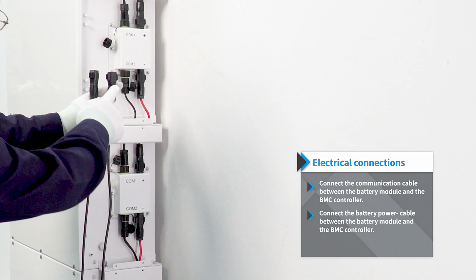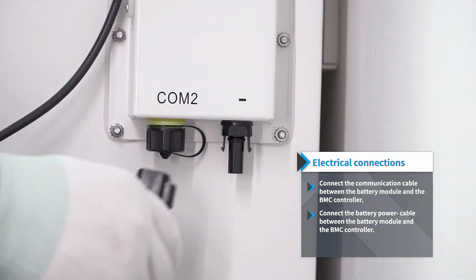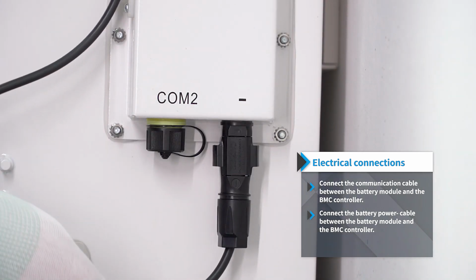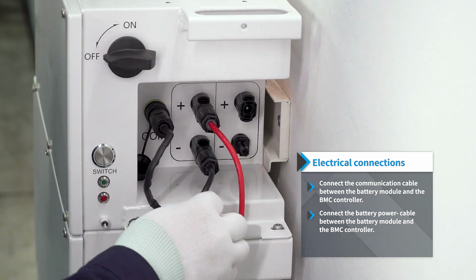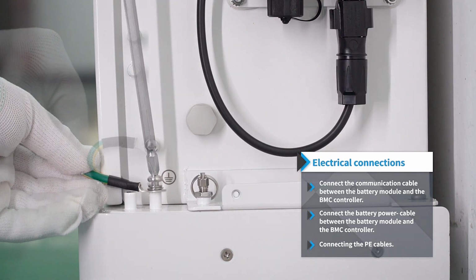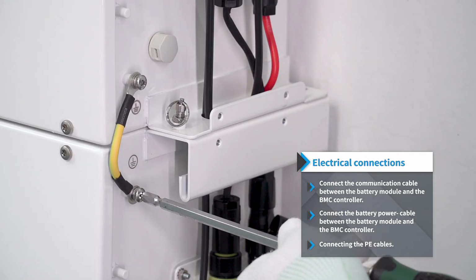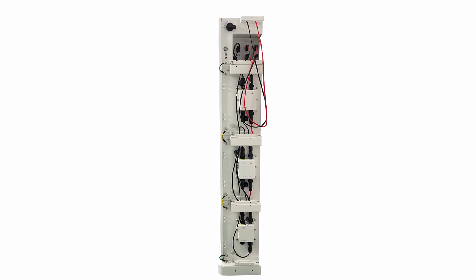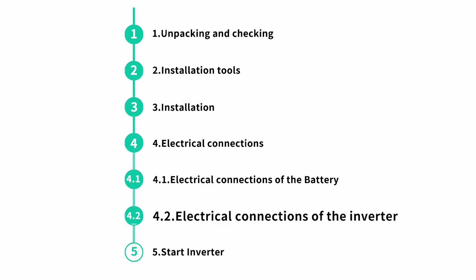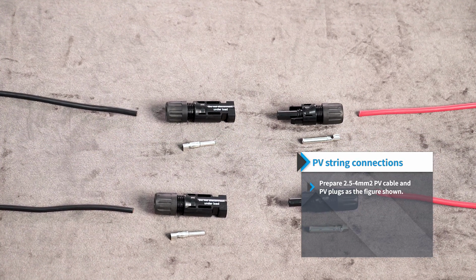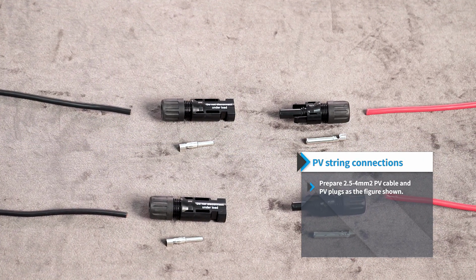Connect the battery power negative cable between the battery module and the BMC controller. Connecting the PE cable. Electrical connections of the inverter. Prepare 2.5 to 4 square millimeters PV cable and PV plugs as the figure shown.